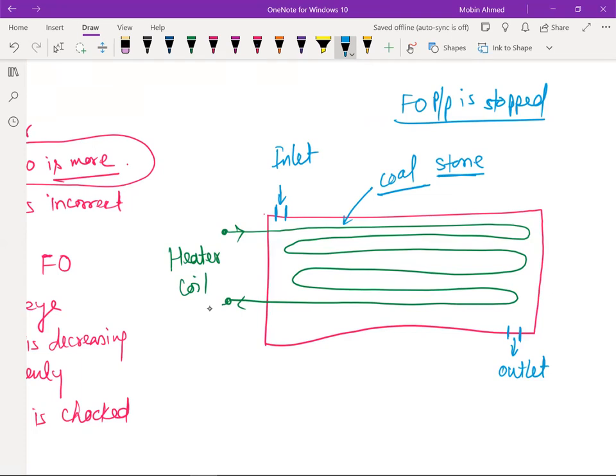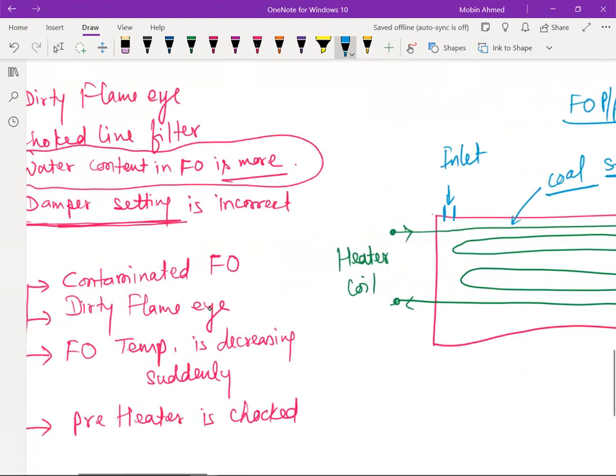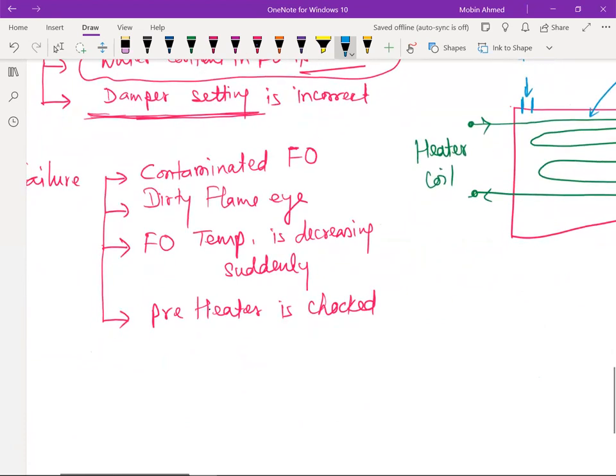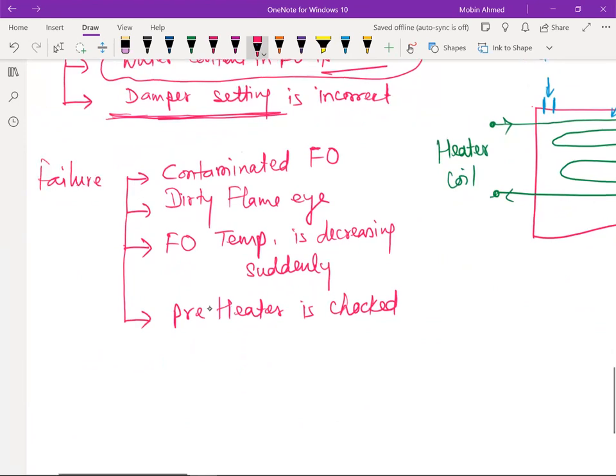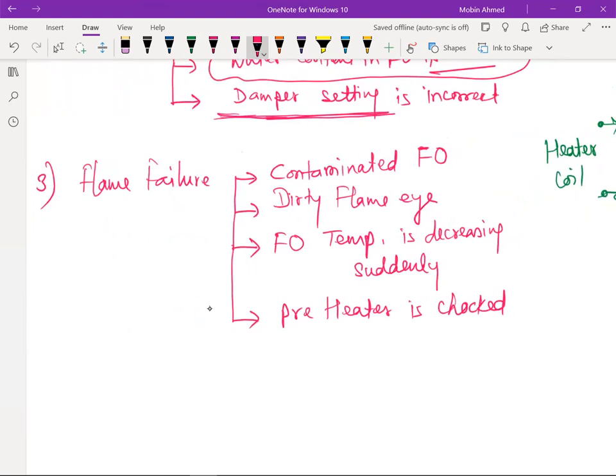So the FO passing through is going to have a temperature, but this temperature is going to decrease suddenly. And this is the reason your preheater is choked. This will be a problem. So your FO temperature is not maintained, and this is the main reason for your flame failure. Otherwise, there should not be any reason for the failure. Once the flame has started, it is supposed to stay.